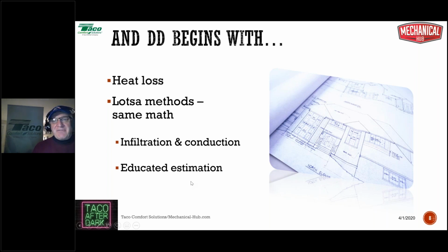In reality, I think everybody here knows the only way to do a real infiltration load is to do a blower door test. But if the house is under construction, you really can't do that. And if you don't have a blower door, you can't really do that for a boiler replacement. So you have to do what we call an educated estimation.